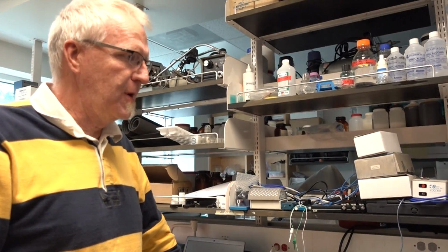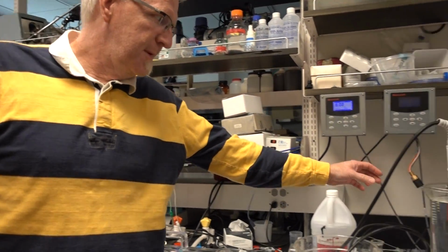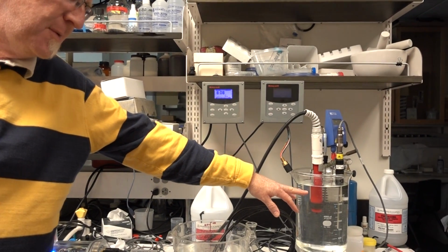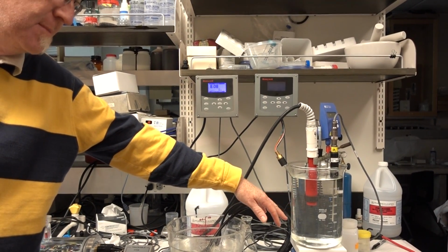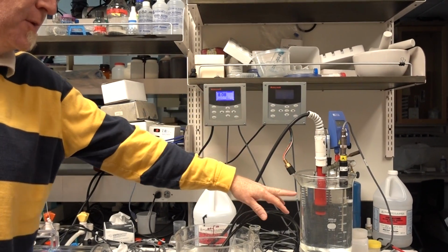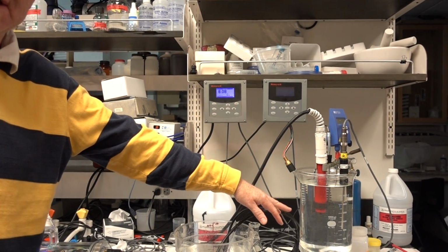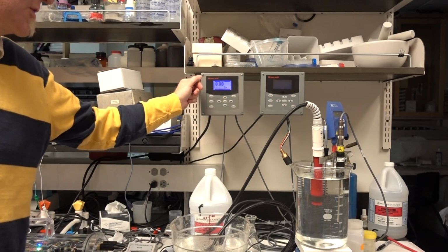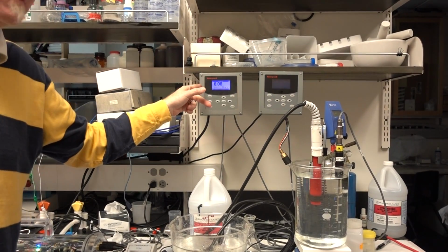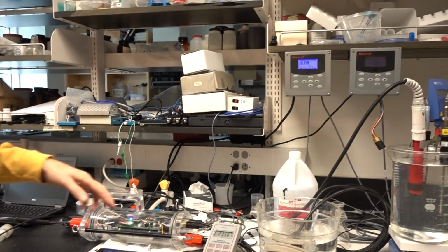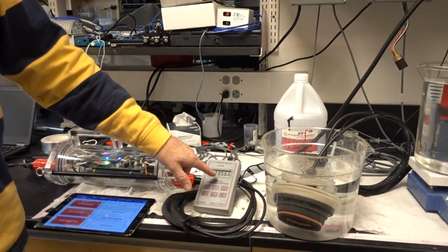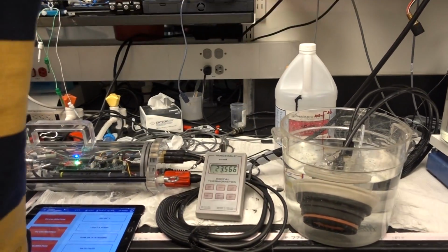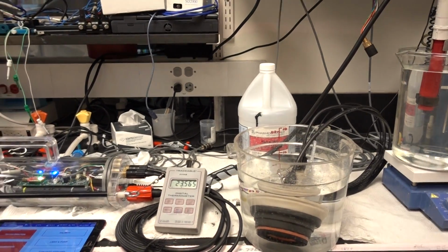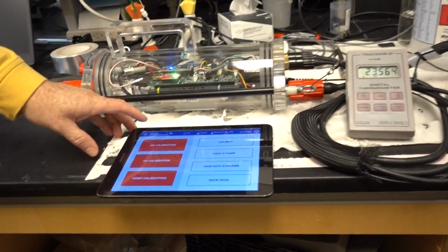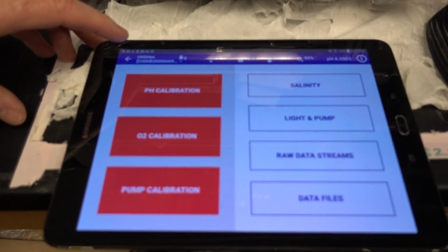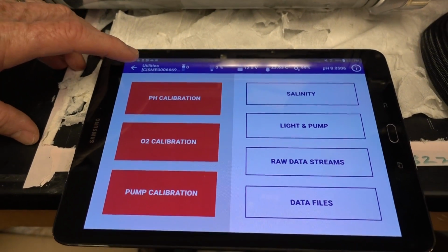So for the pH calibration, we're going to have our electrode out of our pump head and into a container of water that's at a known temperature and a known pH. Normally we do this spectrophotometrically to get the pH, but for this demonstration we're just using our other Honeywell electrode as the reference electrode. We also have a temperature probe in that we're going to calibrate the temperature of our CISME electrode. The electrode should ideally be on for at least 1 hour powered up before you attempt a pH calibration.